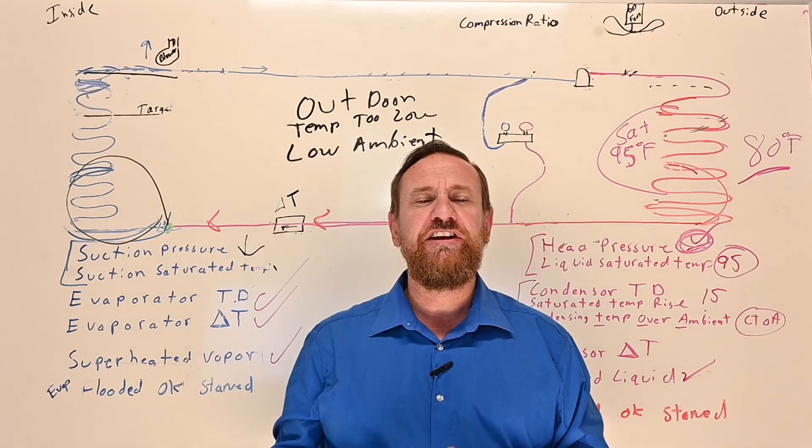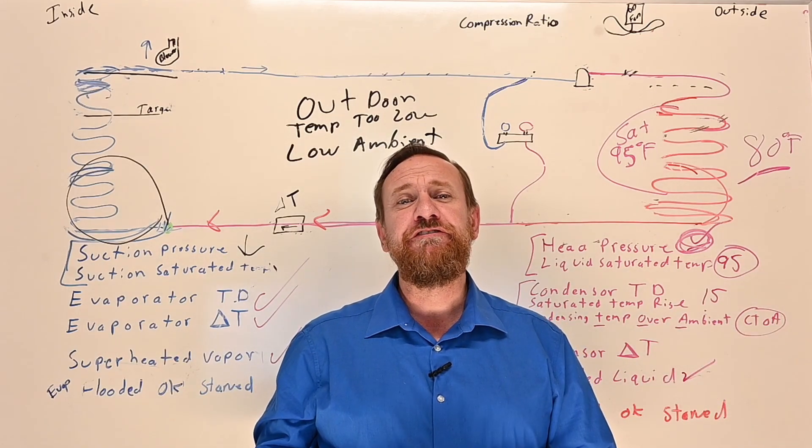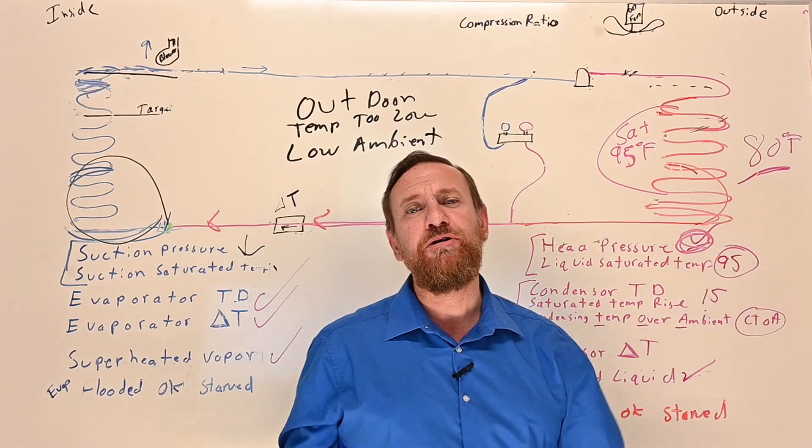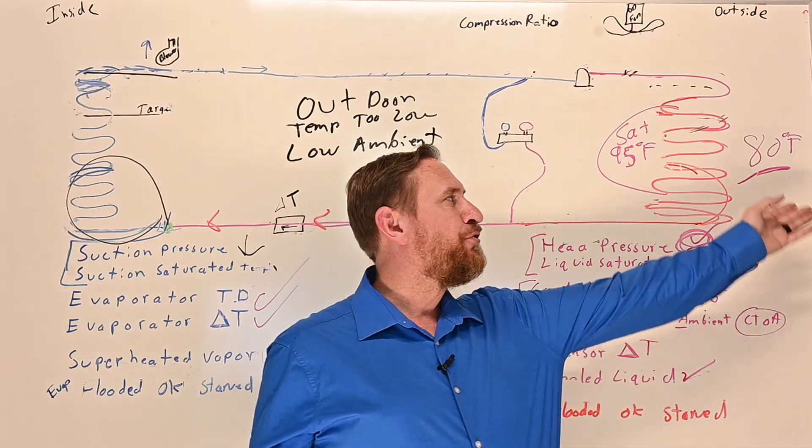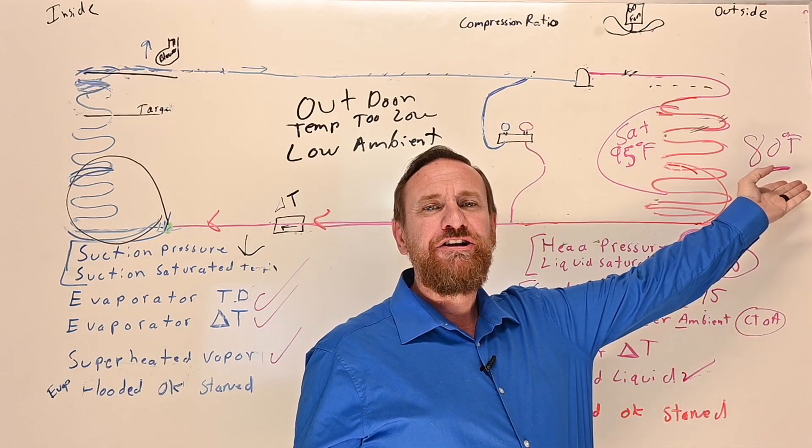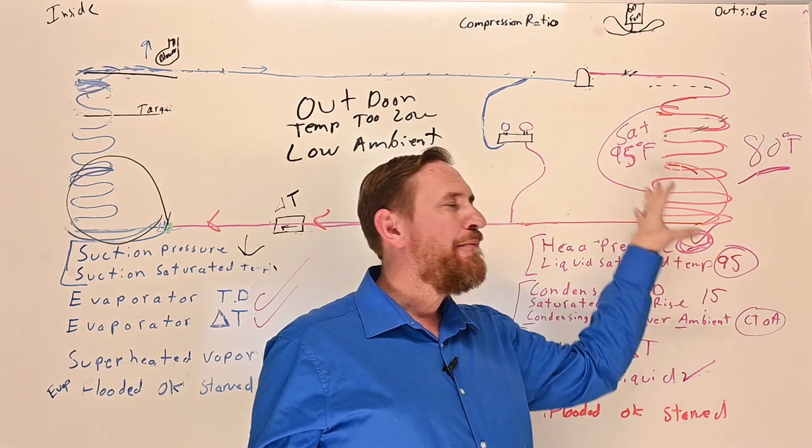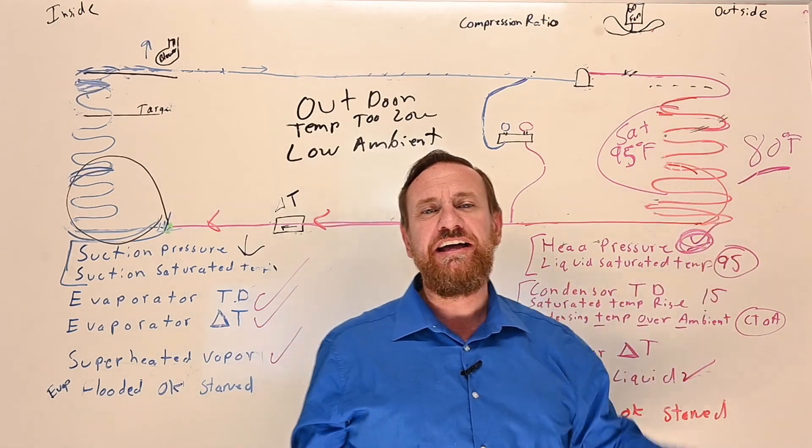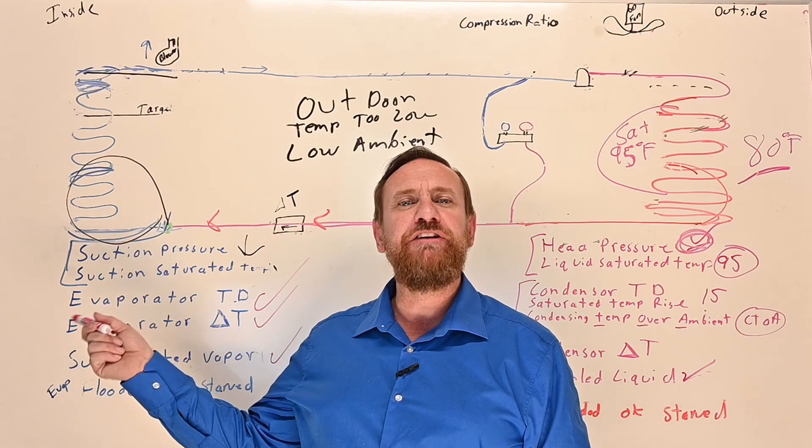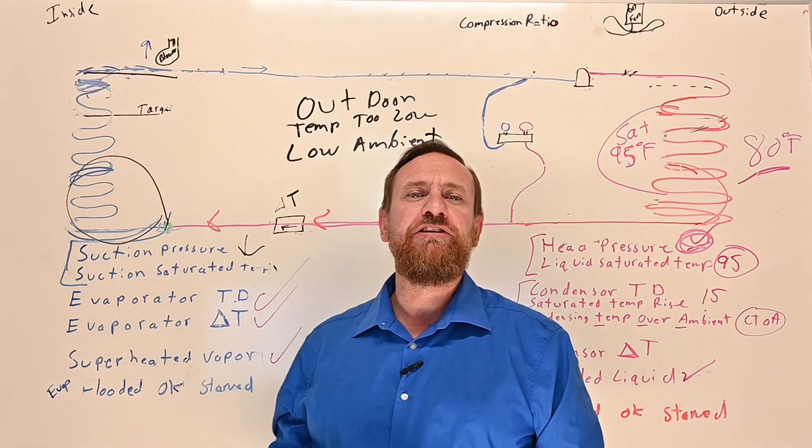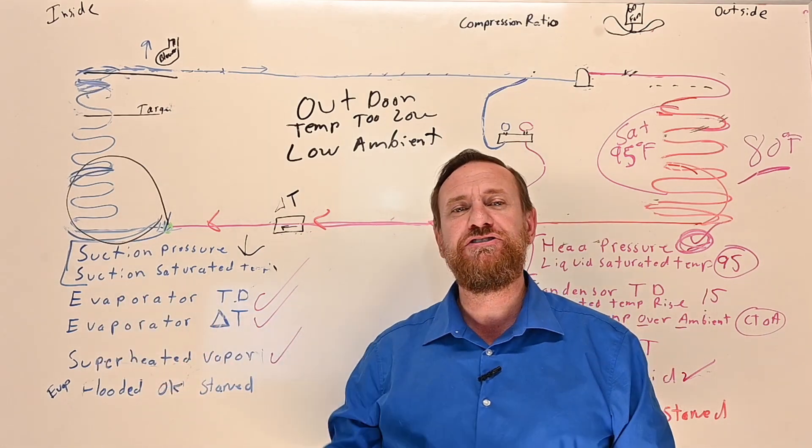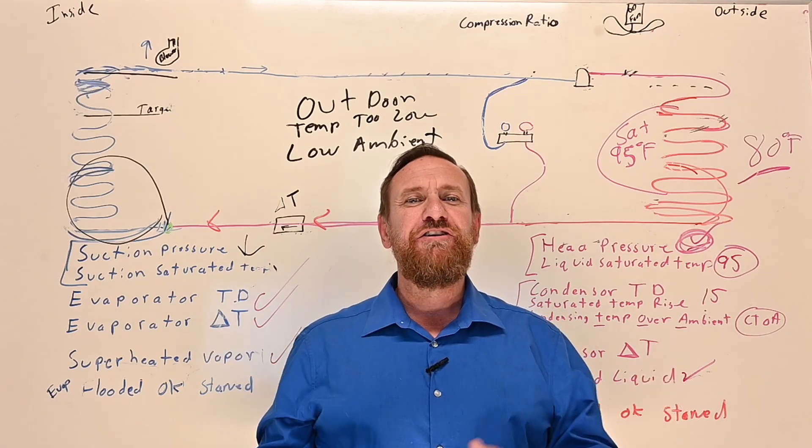So if we're doing maintenance on a system that has a fixed orifice, we need the outdoor dry bulb return air wet bulb. Well, the outdoor dry bulb I'm going to use is going to be my 80 degree day because that's what I'm simulated by blocking the condensing coil. So I'd use that and then whatever my return air wet bulb is with the chart or formula and found out my target superheat. Then see if your superheat matches your actual superheat. Then you know if you're charged right or not.